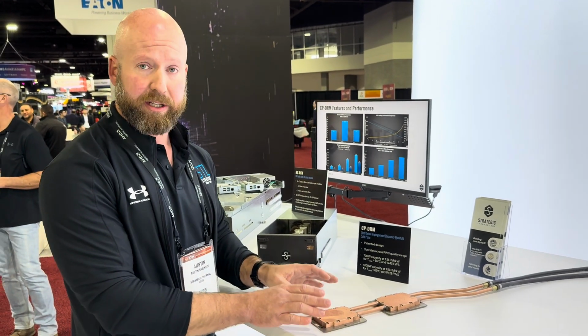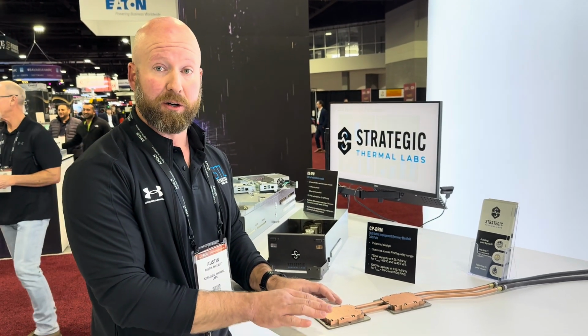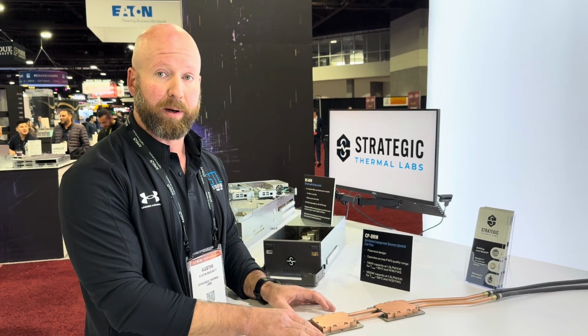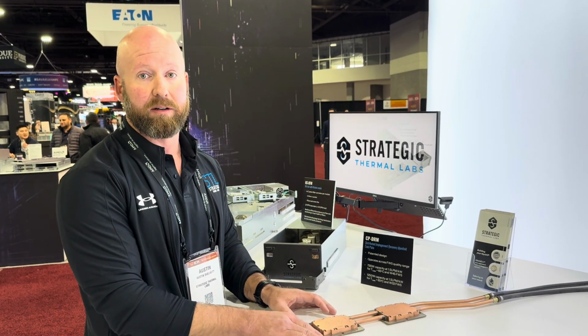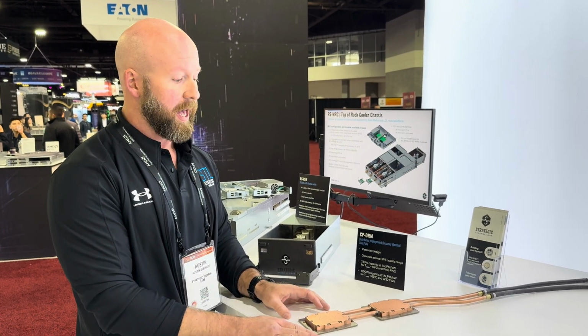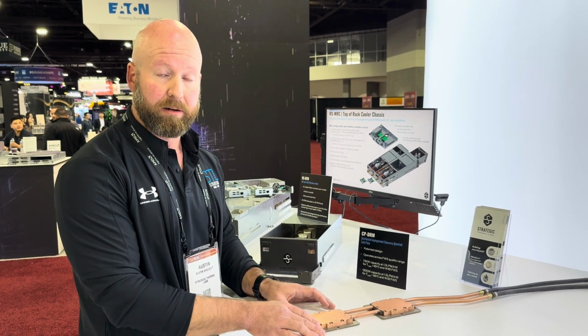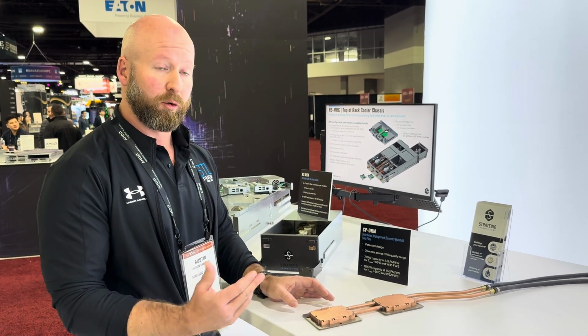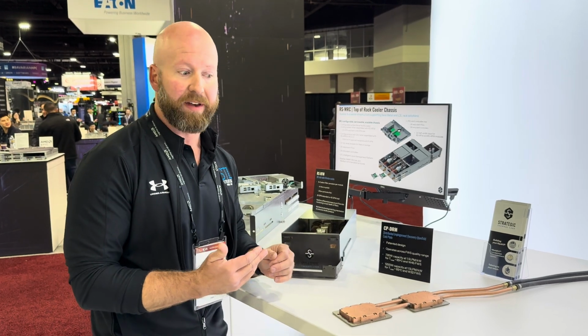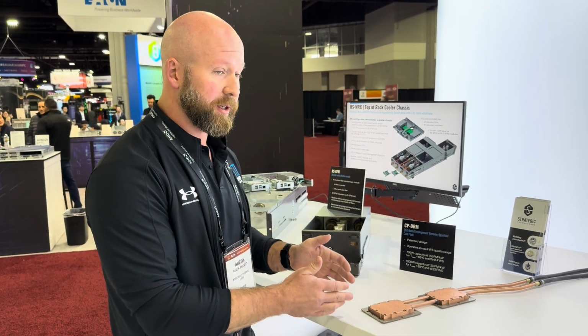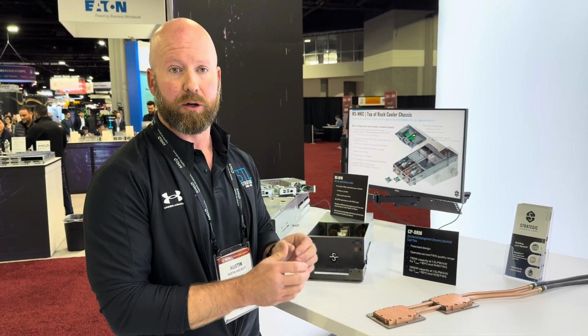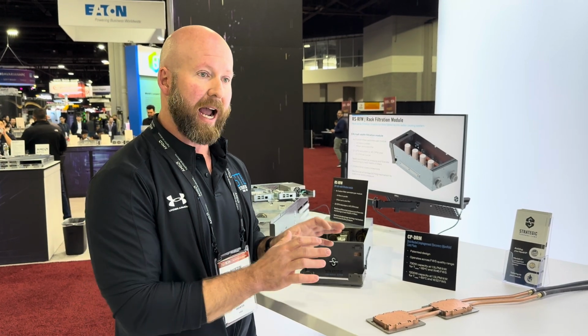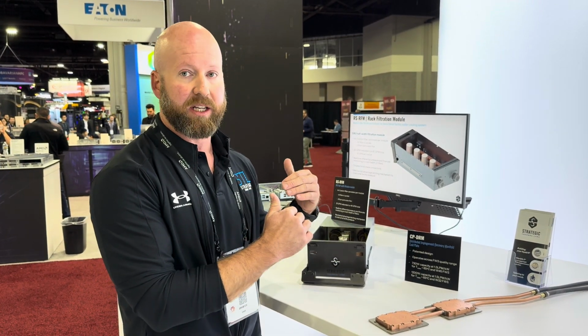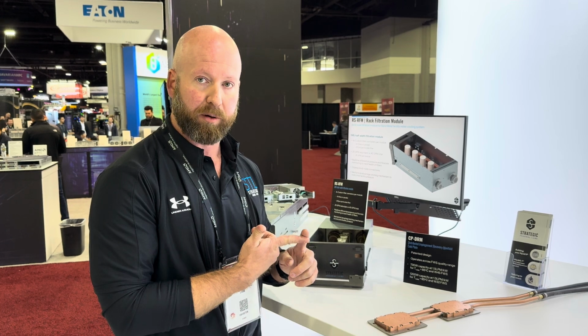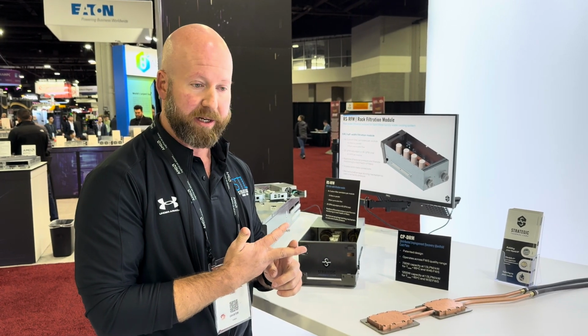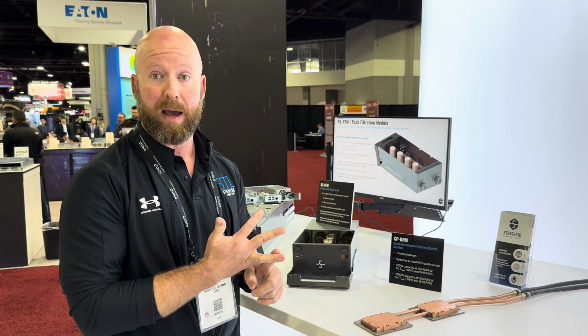Now, I just want to say, we also make cold plates that are designed for CDUs, and those cold plates we can get down to a 50 micron channel, or a micro channel. These are 600 micron, so they're designed so that you don't have to worry about solid particles fouling up the fins. They're also designed to operate at 300 psi. So we've taken the approach, let's design the cold plate to be in the worst case conditions, both from a water quality perspective, from a solid particle perspective, and from a pressure perspective that a building might possibly throw it.